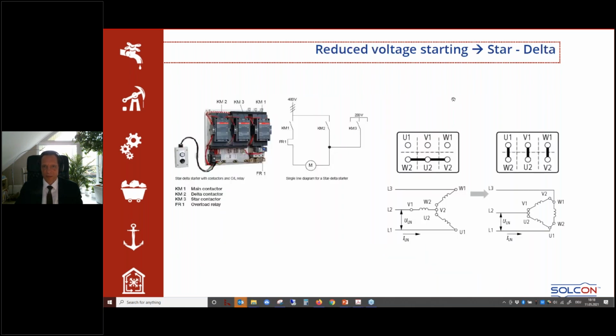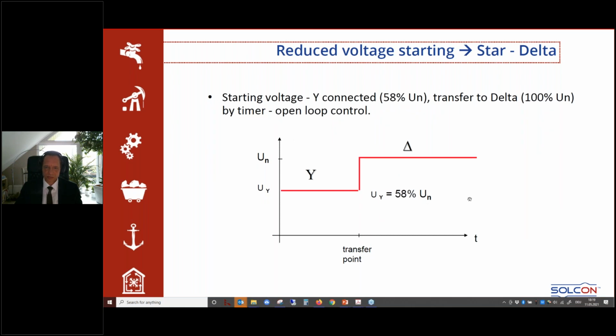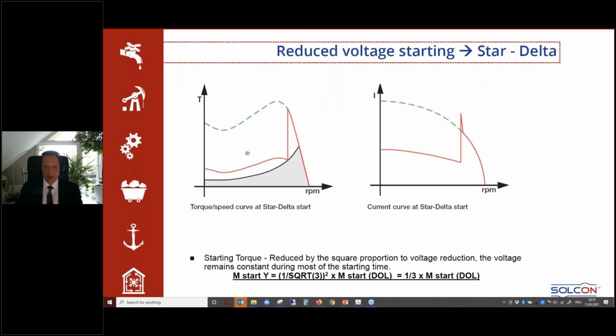You have reduced voltage starting, where you first connect in star and later on in triangle. This is mainly for low voltage, not applicable, let's say, for the medium voltage. It is fixed. You have the starting voltage here, 58%, and here you have the full starting voltage. With it comes a large reduction in starting current, starting torque, and also here in current. If it works, it's fine, but in most cases for medium voltage, not a viable option.